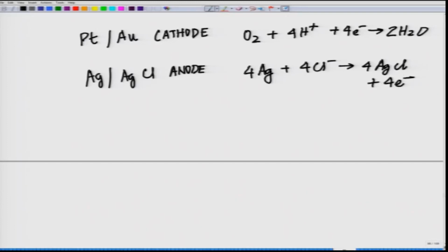A Clark's electrode is calibrated by placing it in a solution of known oxygen concentration, and a graph of current versus oxygen is constructed. Okay. So, basically based on the oxygen concentration, your current is going to change. The electrode also contains a silver guard electrode extending most of the way to the bottom. The guard electrode is kept at negative potential, so that any oxygen diffusing in from the top of the electrode is reduced and does not interfere with the measurement of oxygen diffusing through the silicone membrane at the bottom.